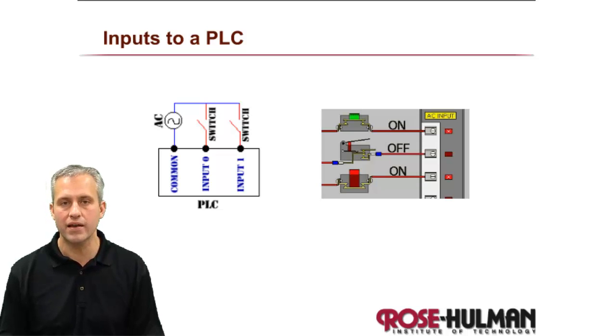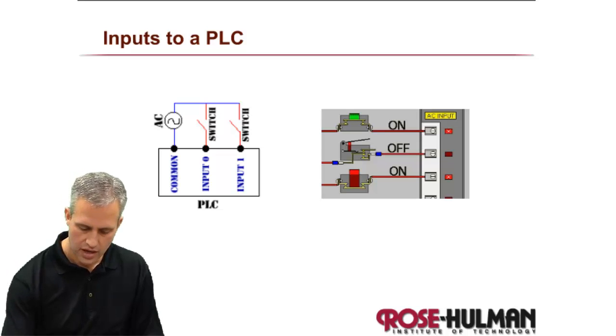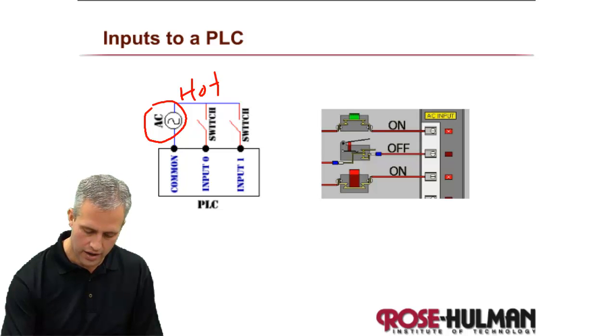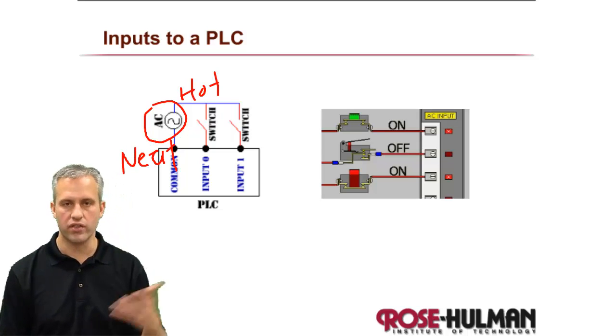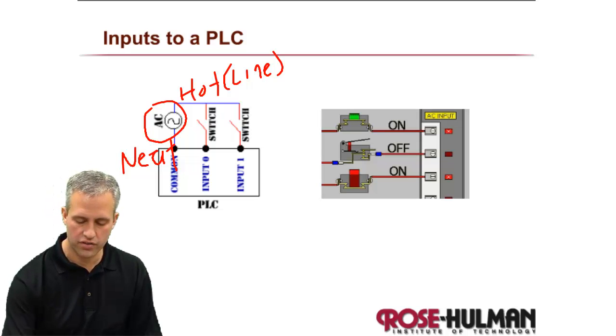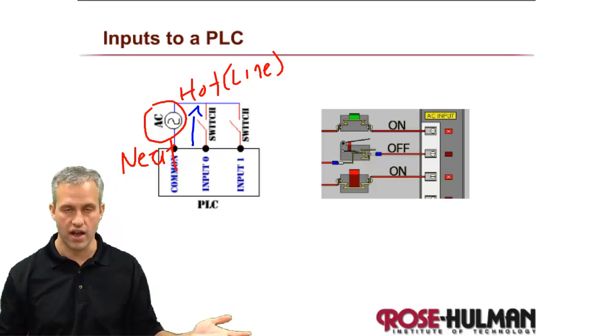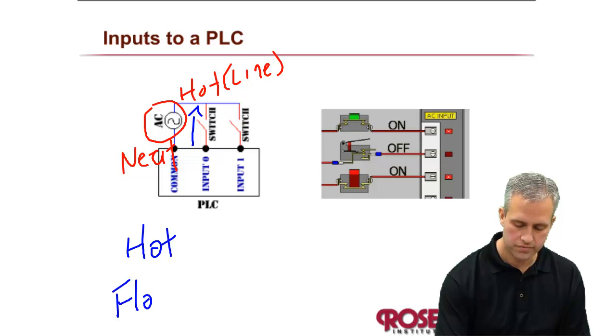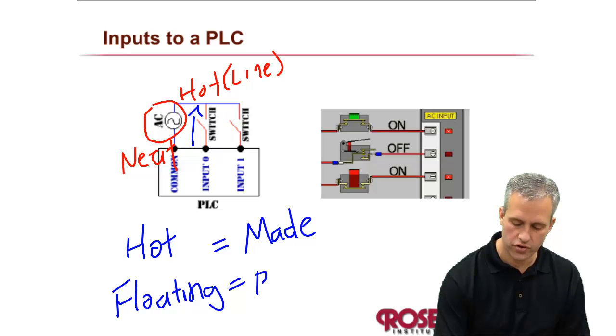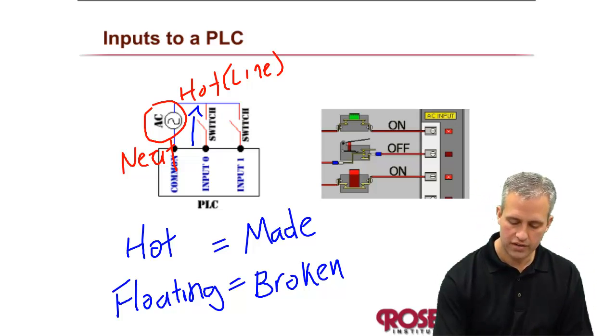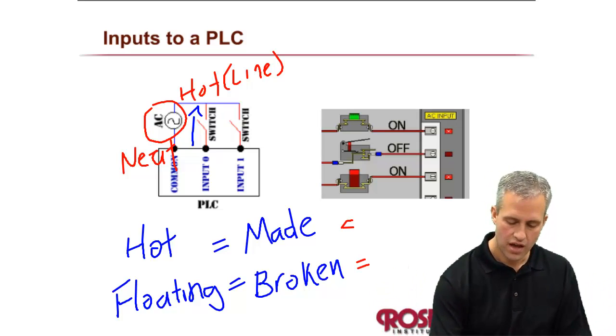Welcome back. This time we're going to talk about inputs. The way inputs work on a PLC is there is an AC source — at least in ours it's AC — and then there's a hot and a neutral line. Hot is also called line. In the simplest fashion, an input is either connected to hot or it is not — typically just floating.